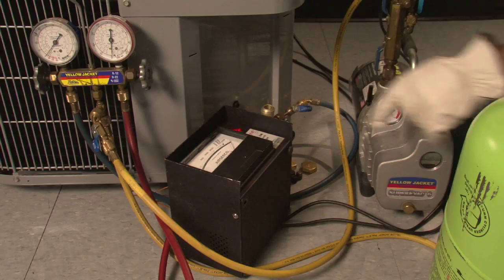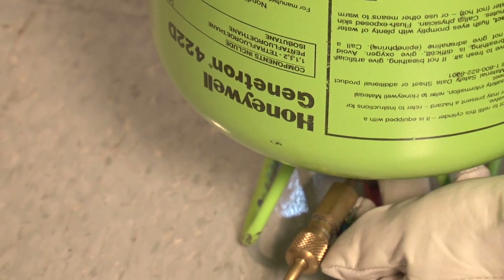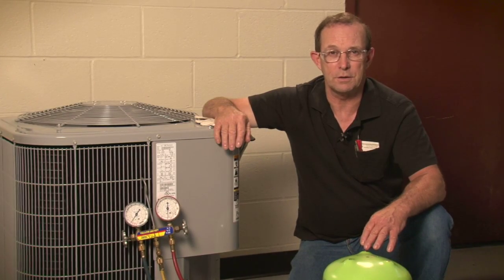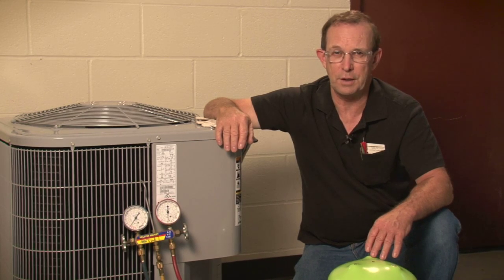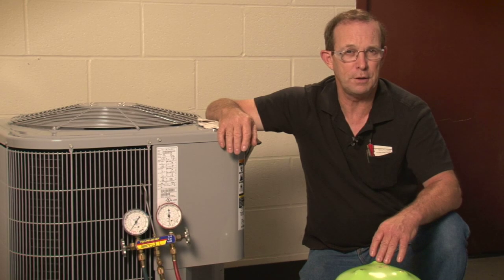Evacuate the system or line set and charge with Genetron 422D as per Honeywell's literature. Use your system operating conditions — suction pressure, discharge pressure, suction superheat, liquid subcooling, and compressor amps — to properly charge your system.